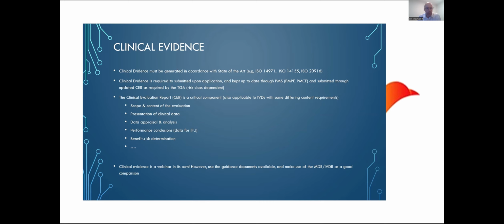Same requirements as Europe. Clinical evidence must be generated in accordance with state-of-the-art standards, such as 14971 for risk management, 14155 or 20916 for clinical studies using samples from human origin. And clinical evidence is required to be submitted upon application, but also kept up to date, again similar to the MDR and IVDR, keeping your clinical evidence up to date throughout the life cycle of the device. That is similar again through the post-market performance follow-up process and post-market clinical follow-up processes. So you update your CER regularly or in line with your requirements annually.